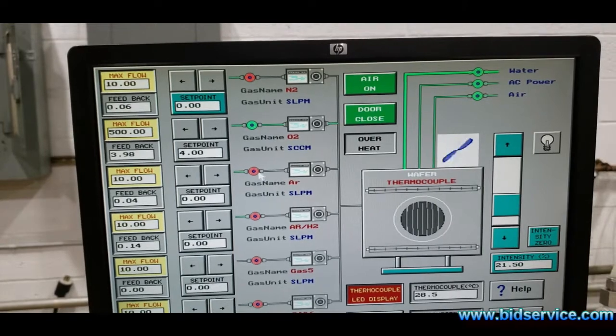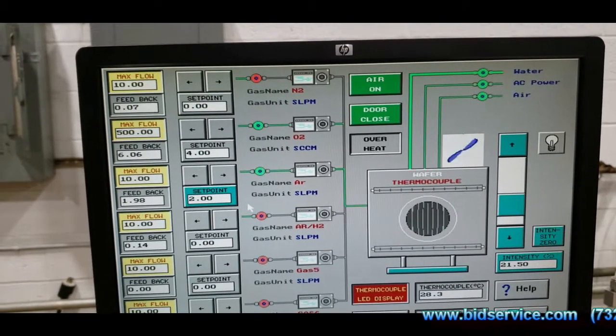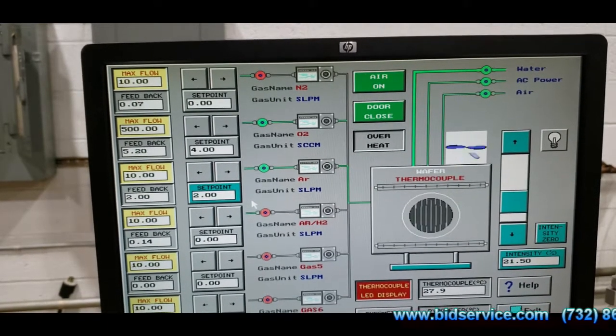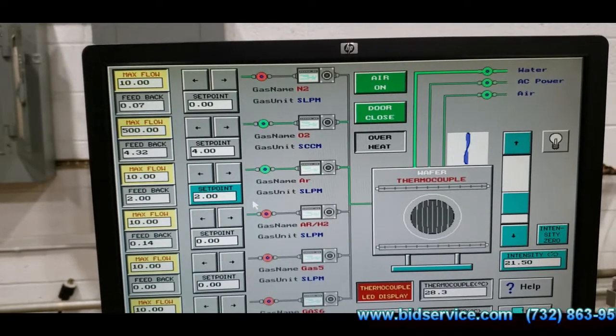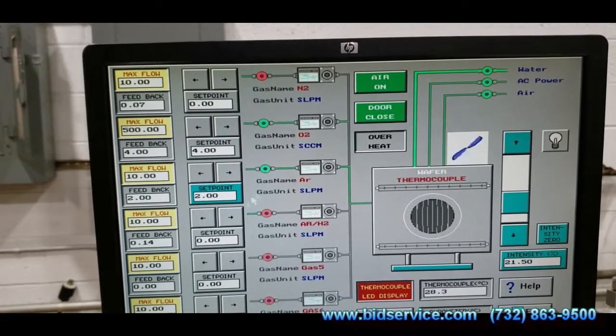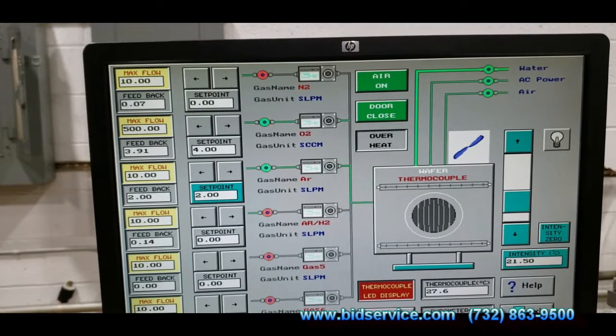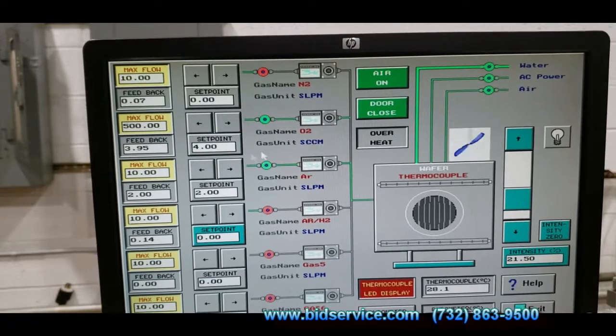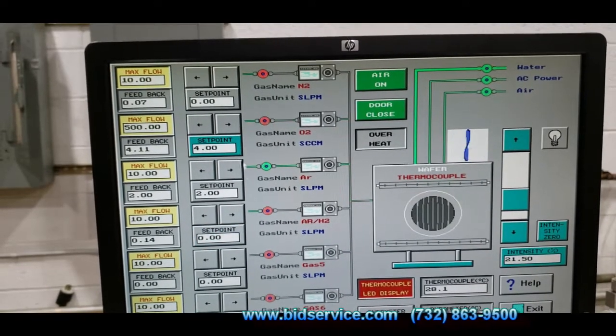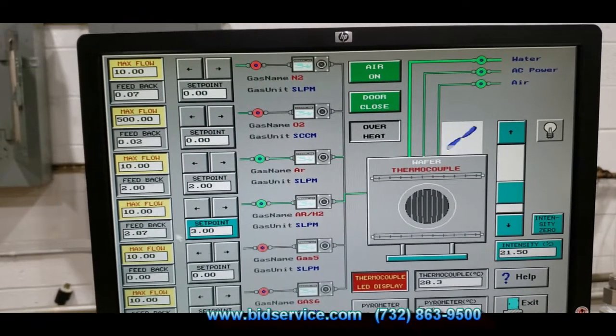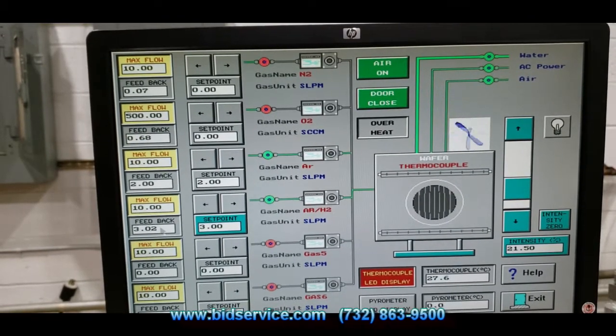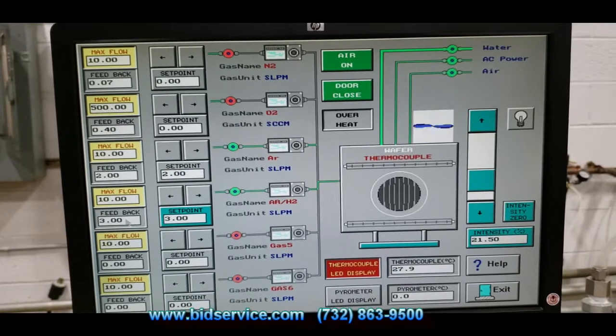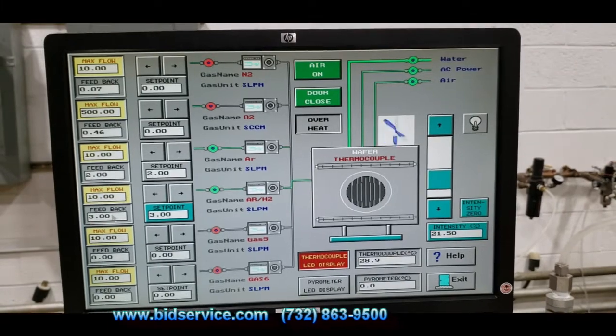I will go ahead and do the third one. I have it set up at 2. And the last one I have it set up at, oh, I can't do that because it is certain gases you can't mix so I am going to turn this second one off and I will put the last one on. I got it set up at 3 and you can see it is coming out at 3. And that is the end of the gas test. And it shows you that everything is working properly.